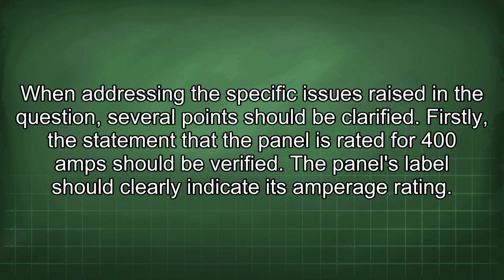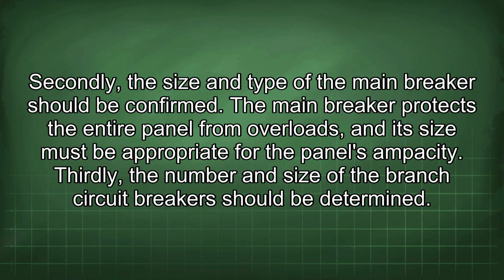Firstly, the statement that the panel is rated for 400 amps should be verified. The panel's label should clearly indicate its amperage rating. Secondly, the size and type of the main breaker should be confirmed. The main breaker protects the entire panel from overloads, and its size must be appropriate for the panel's ampacity.